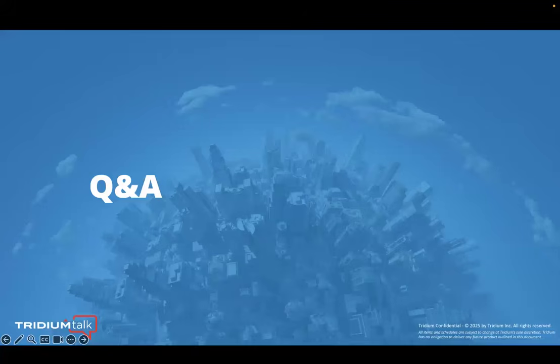So that same port 443 can now be used for both Fox communication to that station and web communication to that station. But it is not a means to do tunneling through one station to get directly to a downstream station. For cases like that, you can use Niagara virtuals, you can use Niagara proxy points, but this is not a replacement for tunneling.